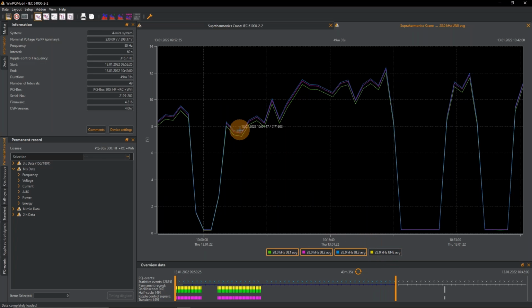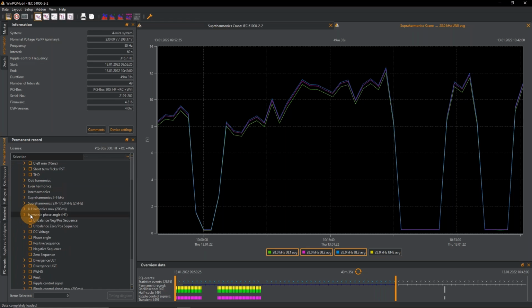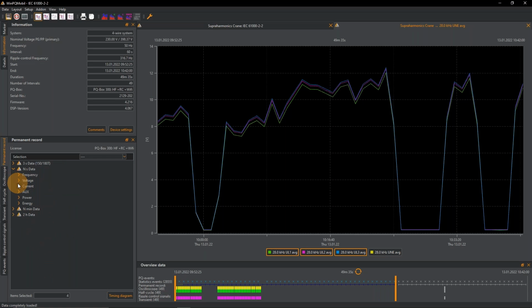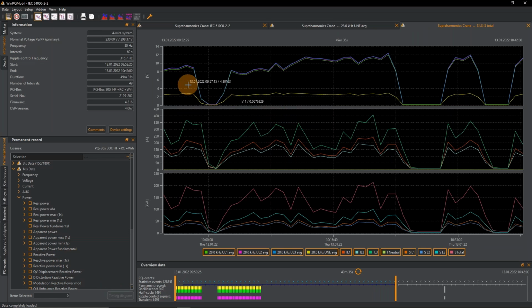If I want to prove that it was really the crane and nothing else, I will just go to my voltage, open the harmonics over here, supraharmonics, the average values, for example, and I select the 28 kilohertz. As well, I could select either the current, for example, or I can also select the power. I just go for the apparent power and display it in one timing diagram. And here I see, okay, supraharmonics at 28 kilohertz every time it was around 8 to 10 or even more volts when, as I promised, the crane system was turned on. So if you want to prove something and measure the current, you're always good to go with the current or the power.